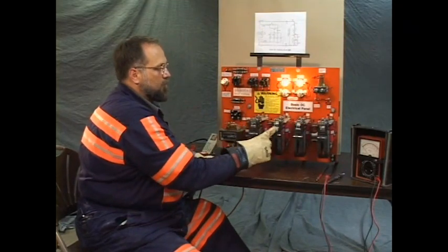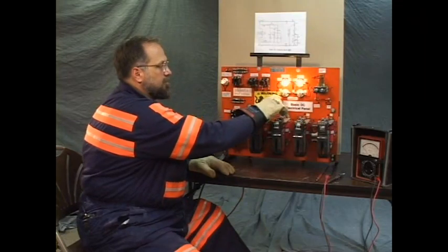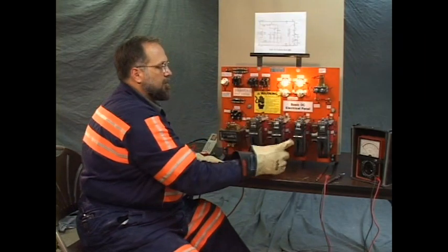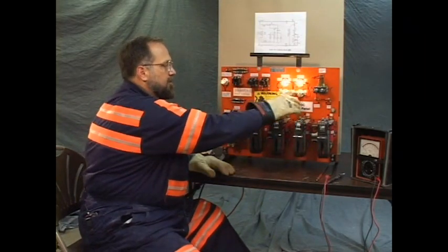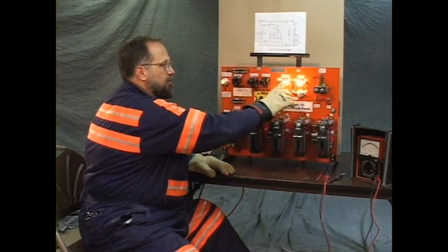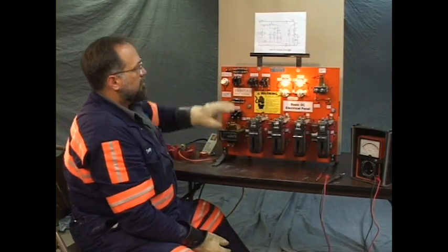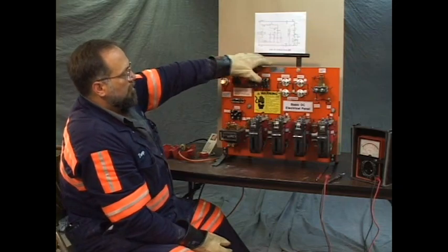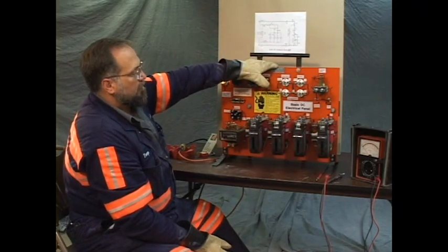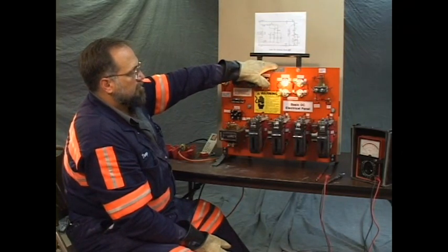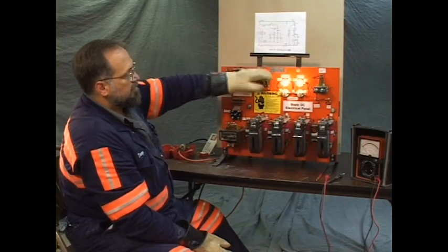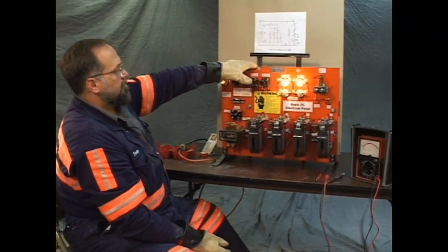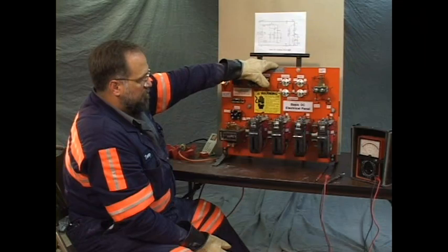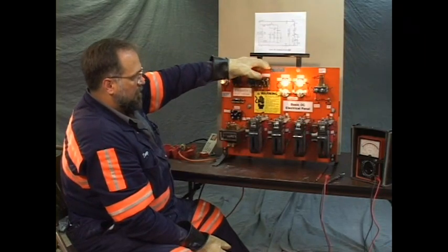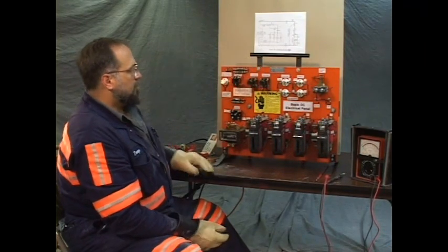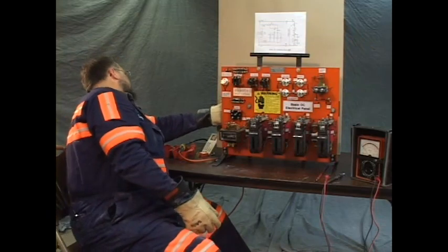After 1 second, when 1A closes, this light goes out. These 2 get brighter. When 2A closes, this light goes out. This one is bright. These 2 are the only ones left. Watch it again. Listen for the contactor action and watch the lights. Hear 3 clicks and you see that pattern. 1 more time. Okay. Now let's install our problem. It's problem number 15.